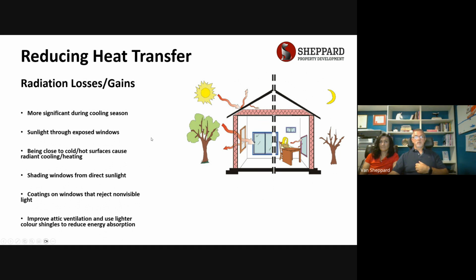The last thing is to improve your attic ventilation and use lighter colored shingles. Again, if you see the top image here, heating on the roof makes it hot. And if you've ever been in an attic in the summer, you know exactly that it can be very, very hot up there. You can't work during the day when the sun's directly on your roof. Those heated surfaces radiate, and some of that radiant energy comes into your building. You want to reduce that. You improve the ventilation in your attic so that air moves better and it doesn't get as hot. And you put a lighter color shingle on your roof, and again, it doesn't absorb as much heat energy. It rejects more. So those are the means you can use to not take in heat through radiation. And if I remember correctly, I think I had to specify the shingles that we were going to use to our energy modeler so he could put that into his model properly.